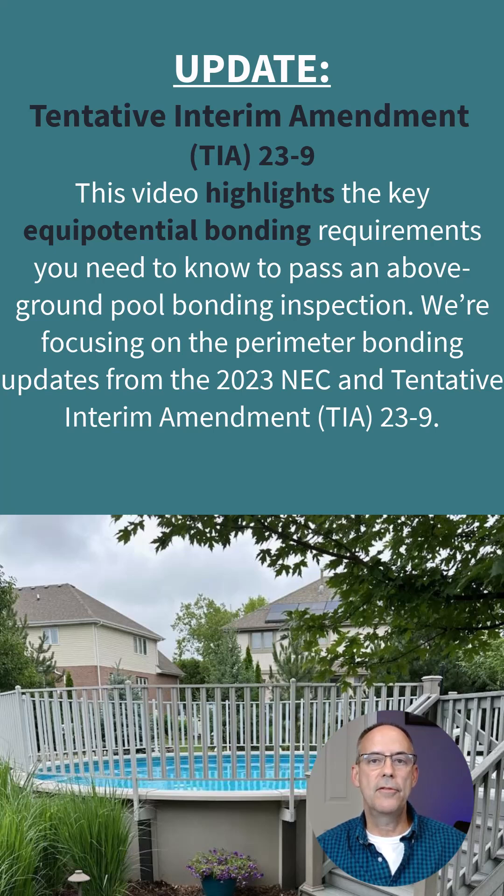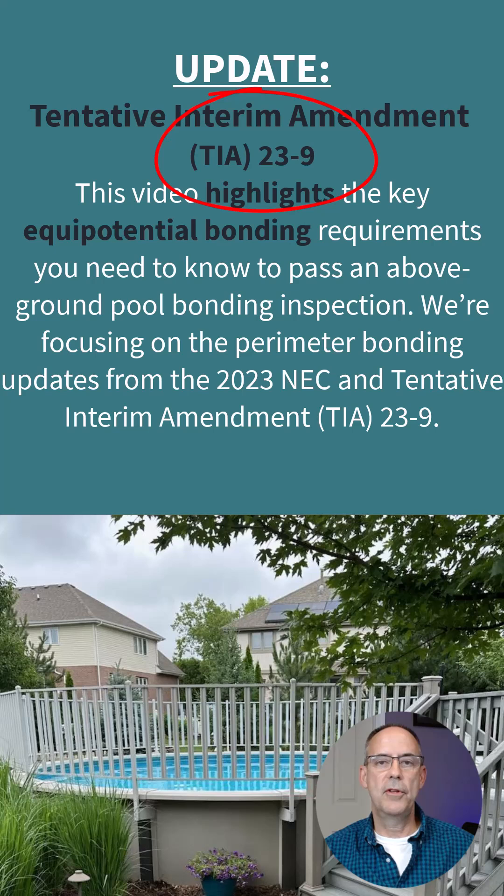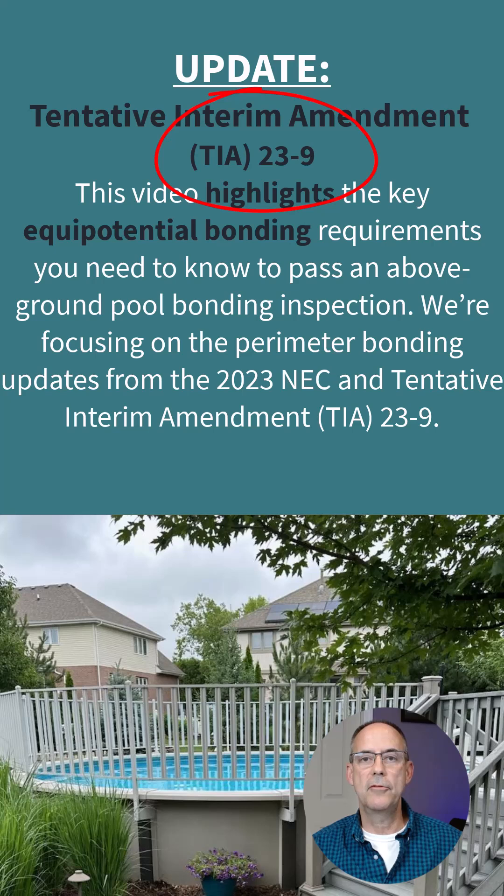References are going to be taken from the 2023 NEC and this video is highlighting equipotential bonding as it applies to the 2023 TIA. TIA 23-9 was issued after the 2023 NEC was published and it has an impact on equipotential bonding, specifically how we look at perimeter bonding and what is allowed now as opposed to earlier cycles.